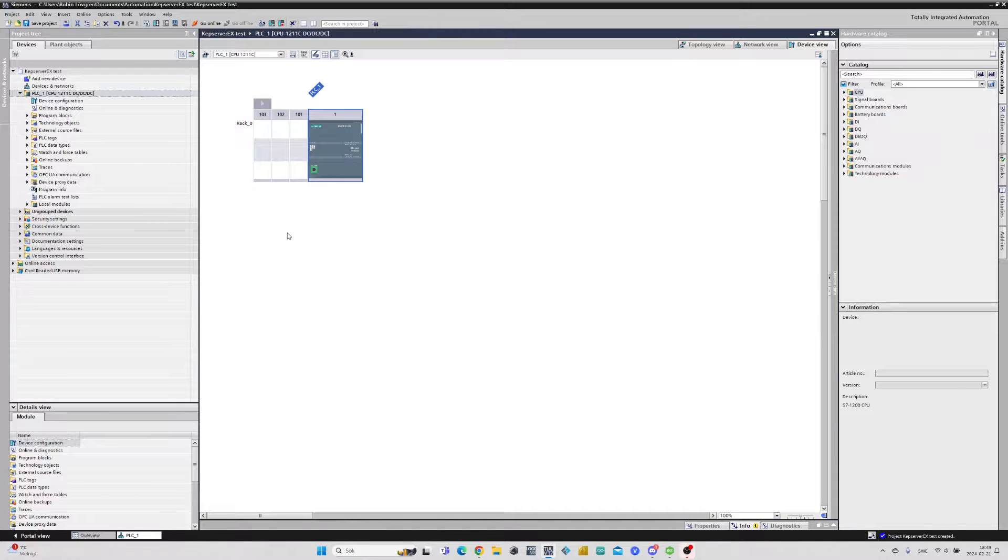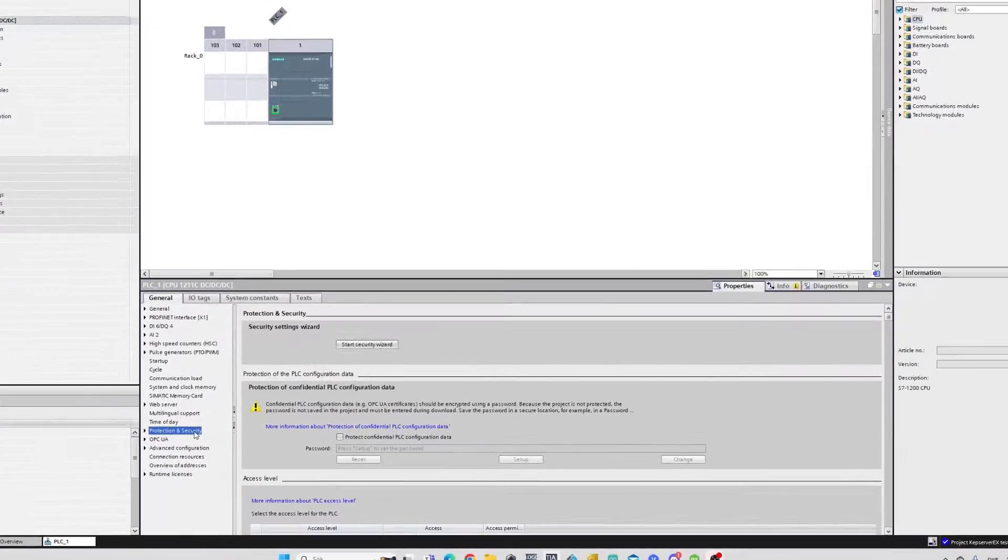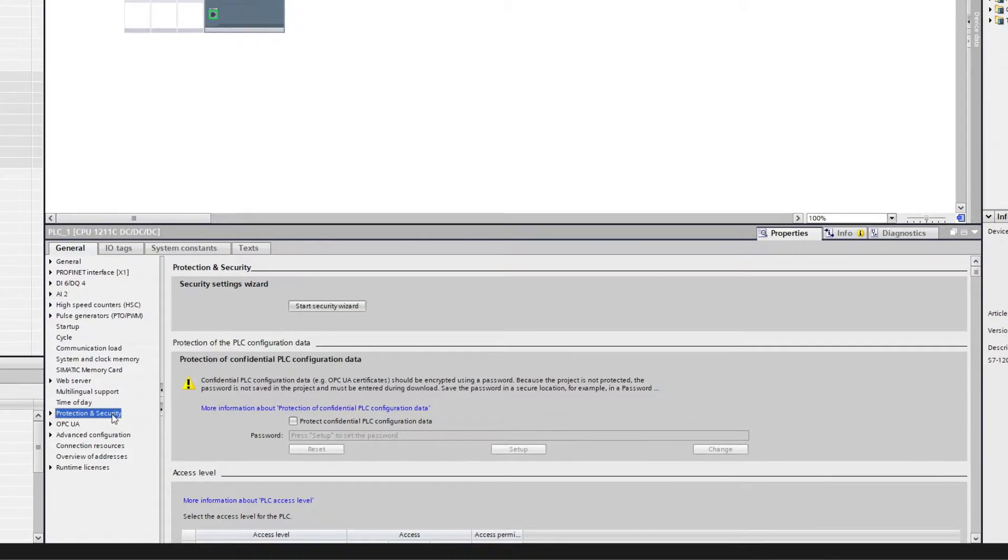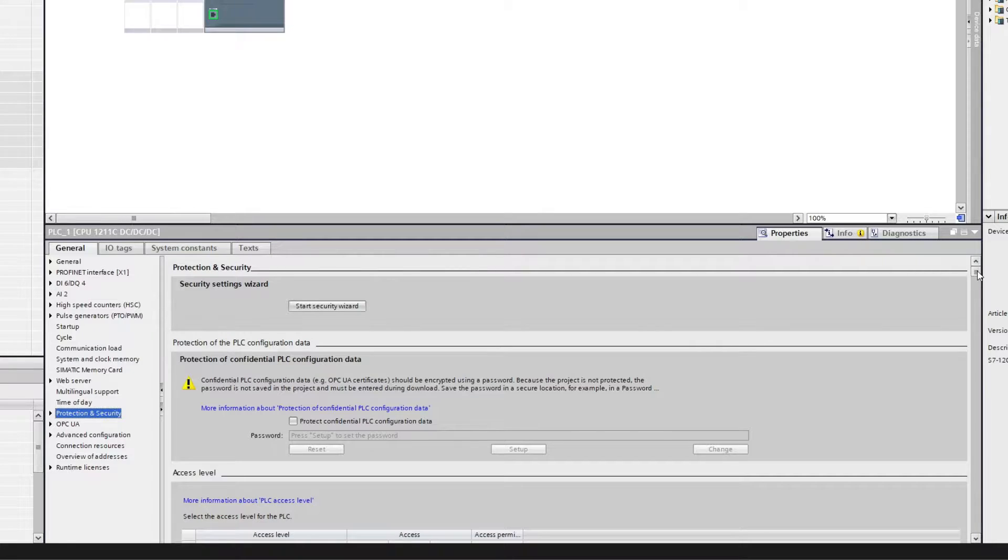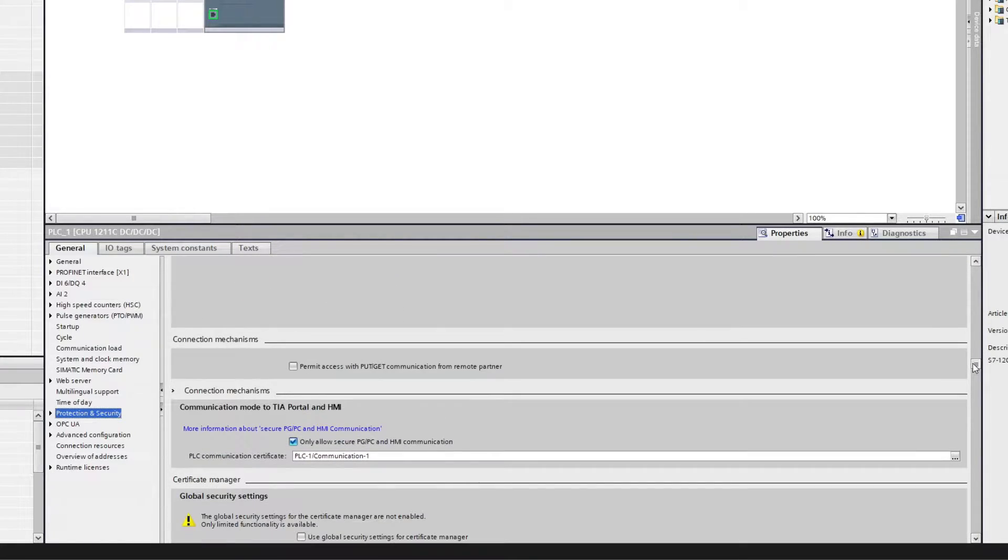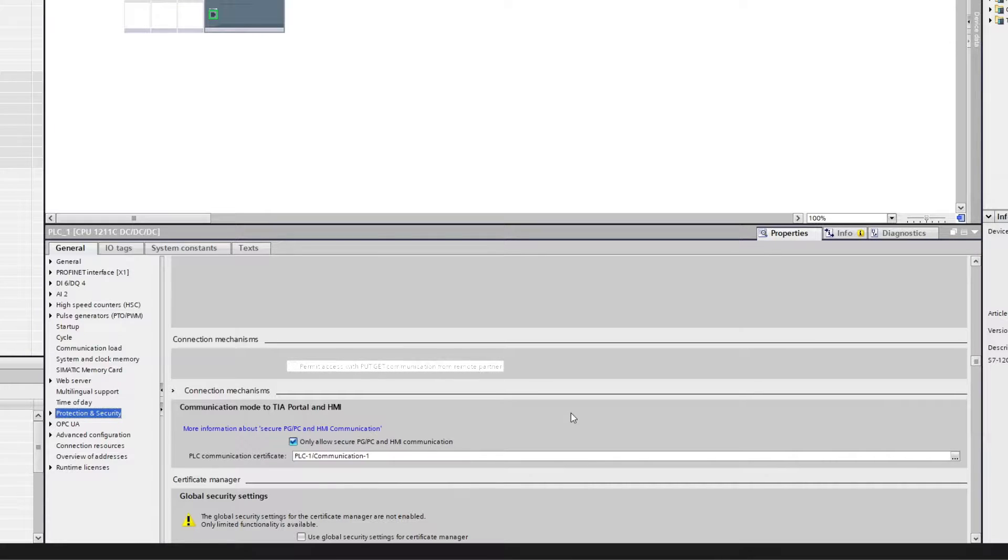Now that we got our PLC added to the project we can click on it to open up the system settings tab. We then need to click on the protection and security tab. If we then scroll down to the column where it says connection mechanism, we will see a box to check which says permit access with PUT GET communication from remote partner. We need to check this box to let the PLC communicate with the OPC UA server.